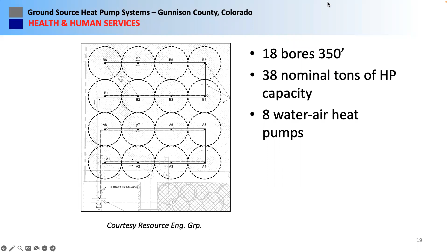Because of the other drilling issues, we decided to limit our design depth to 350 feet, since we figured we're in the same geologic regime, so let's shorten it up a little bit. By the way, every one of these projects had a thermal conductivity test. There's 38 nominal tons of heat pump capacity with 8 water-to-air heat pumps taking care of the conditioning of the facility.